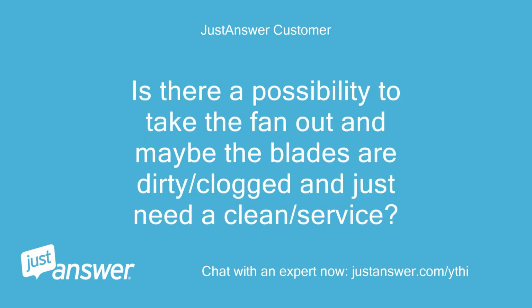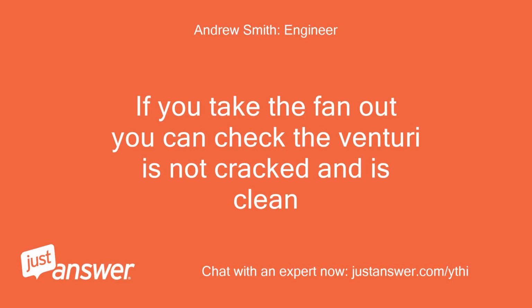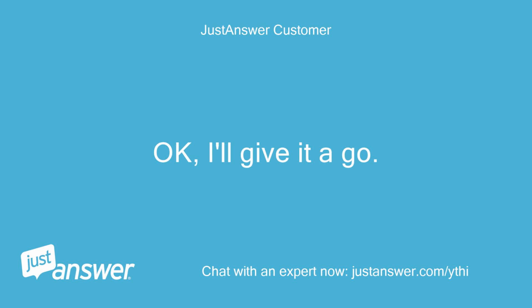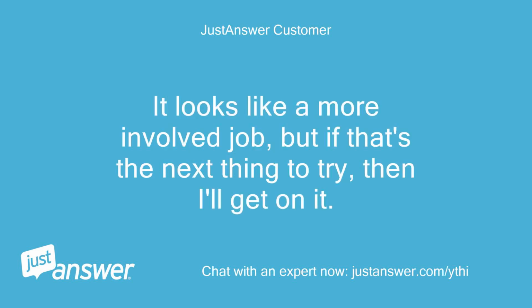Is there a possibility to take the fan out and maybe the blades are dirty or clogged and just need a clean or service? If you take the fan out, you can check the venturi is not cracked and is clean. Okay, I'll give it a go. It looks like a more involved job, but if that's the next thing to try, then I'll get on it.